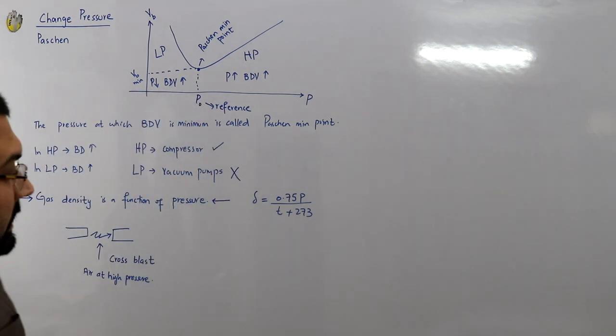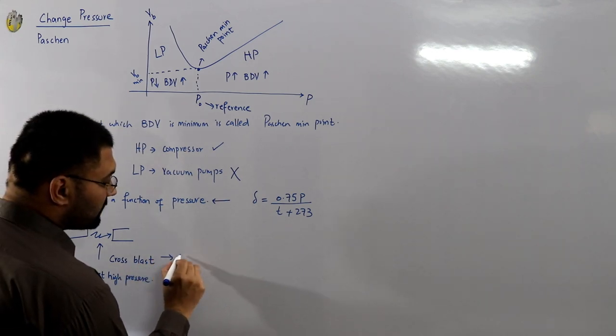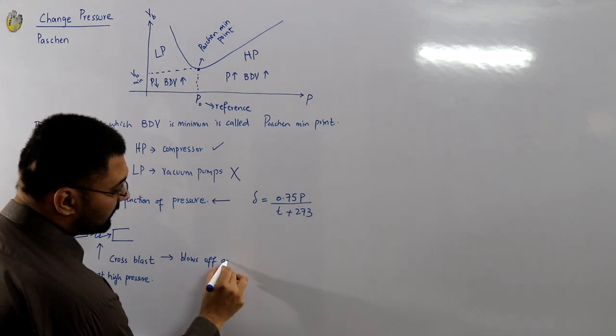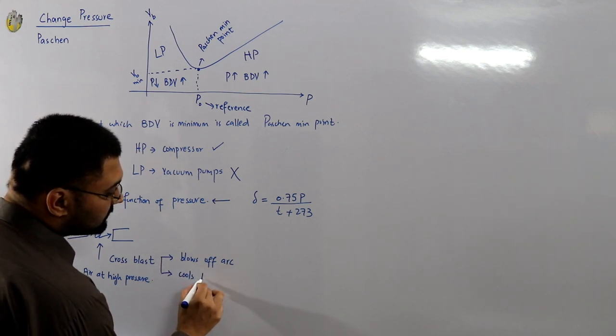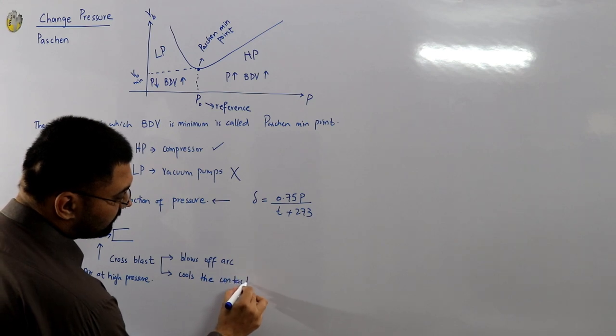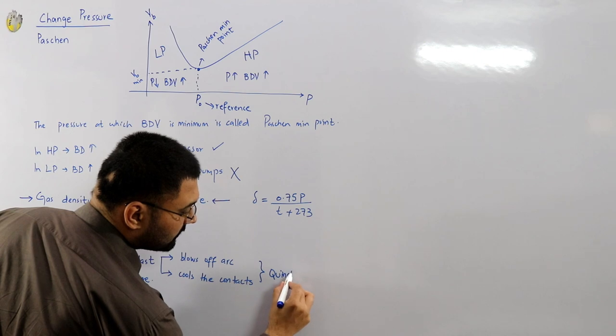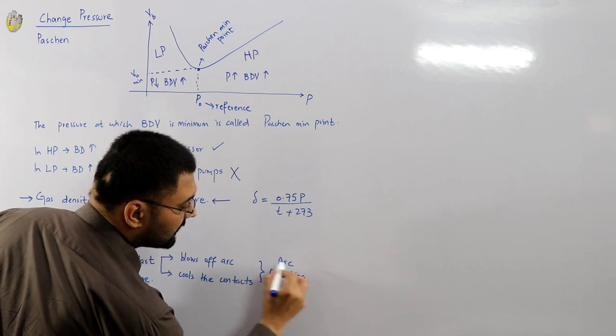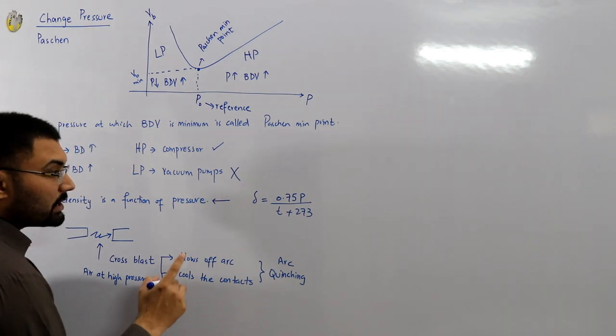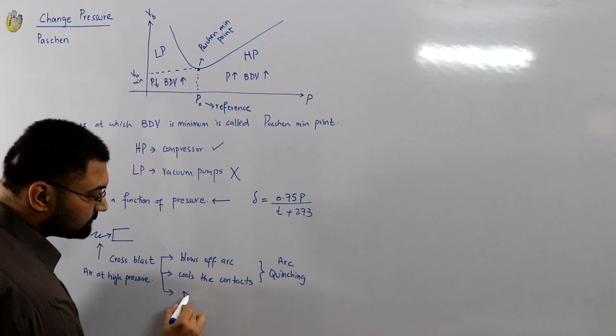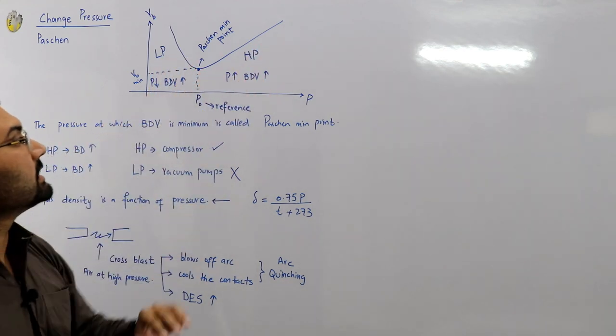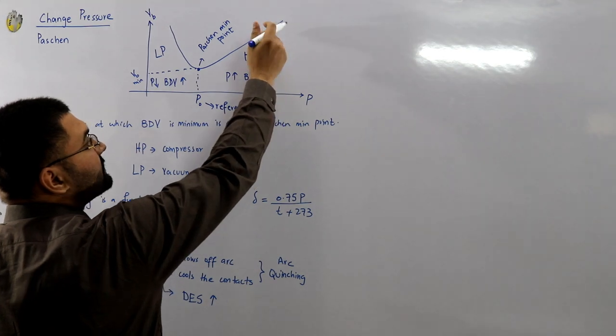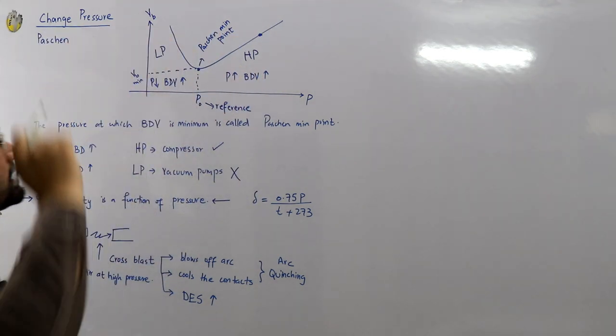This high pressure air does three things. Number one, it blows off the arc — cuts it into fragments and blows it off. This is called arc quenching. Number two, it cools the contacts. Number three, it increases the dielectric strength, because of the high pressure. So you are injecting this pressurized air in the high pressure region, which increases the dielectric strength as well.